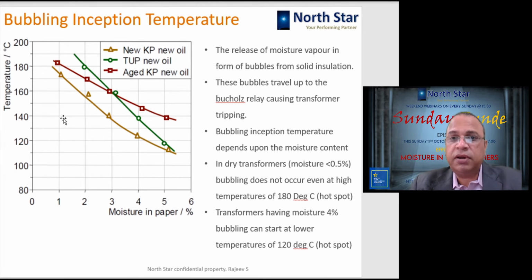So that vapor in the form of bubbles travels, because it is a gas, so it travels up and gets accumulated in the Buchholz relay, and the Buchholz relay gives you an alarm and later on the tripping signal, and the transformer trips. So these bubbles are causing the tripping of the transformer, and the rate of bubbling or quantity of the bubbling will depend upon the moisture content inside the transformer.